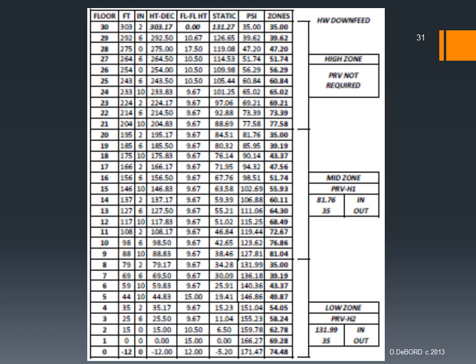So you see the PRV outlet is only 35 psi, and then it's picking up, because it's downfeeding, it's picking up pressure down to the bottom. We can only put 80 psi to a fixture, so this doesn't account for friction. So if we have 81 psi at the bottom of the zone, that's just fine. It's not really going to be 35 to 81 psi at the fixture. It'll drop off a little bit.